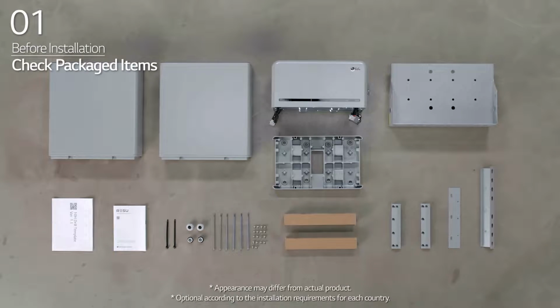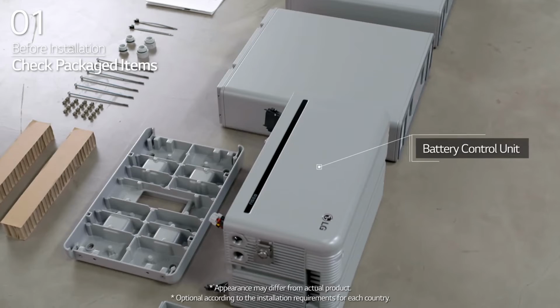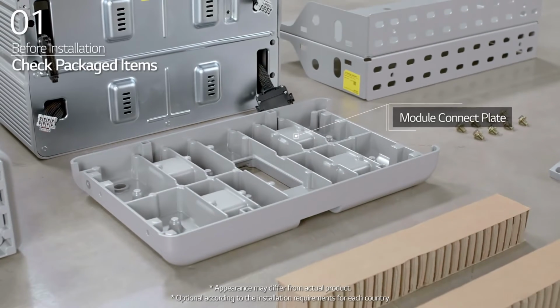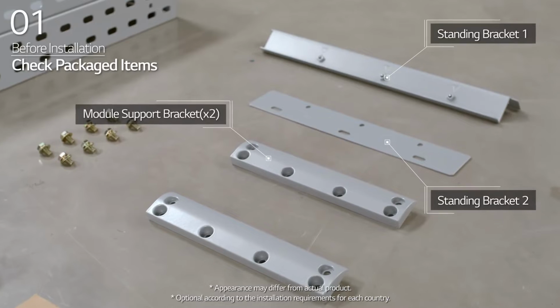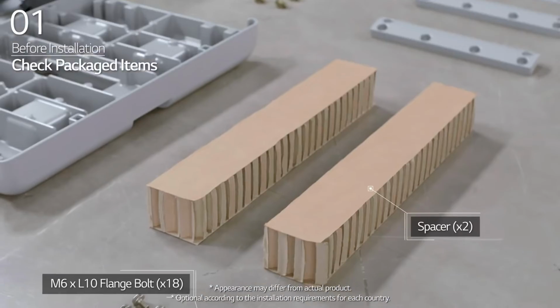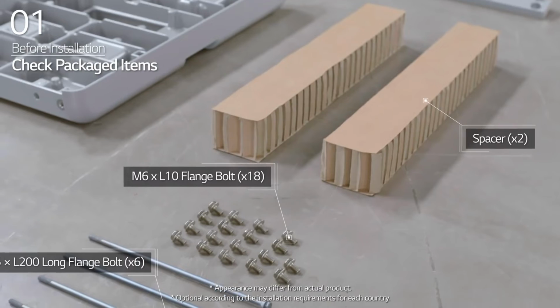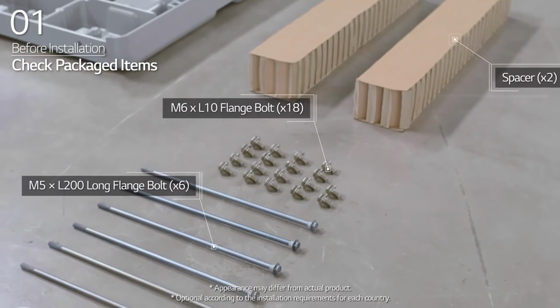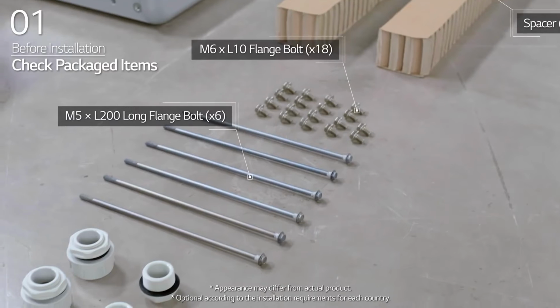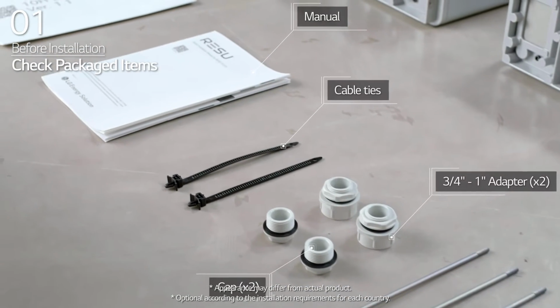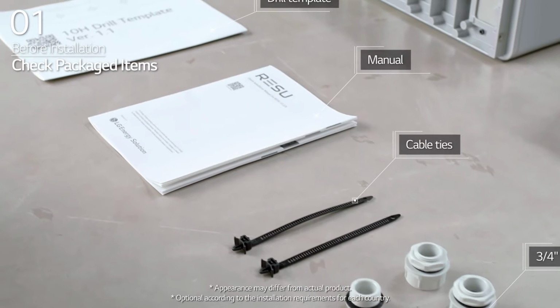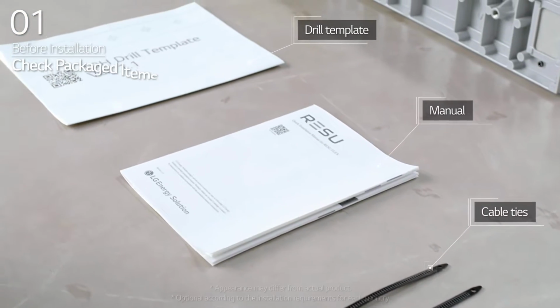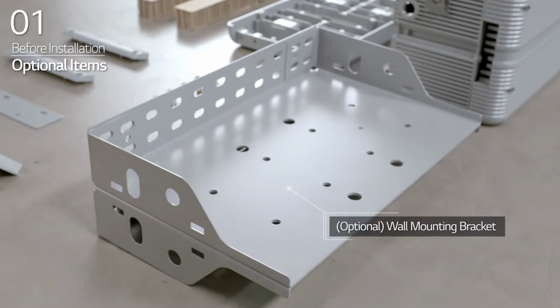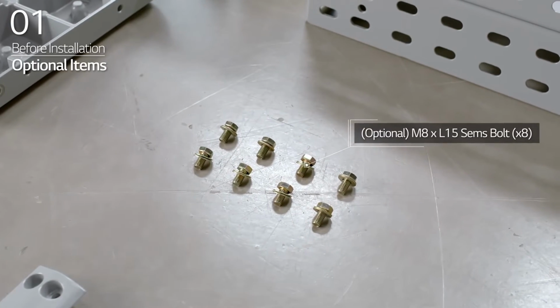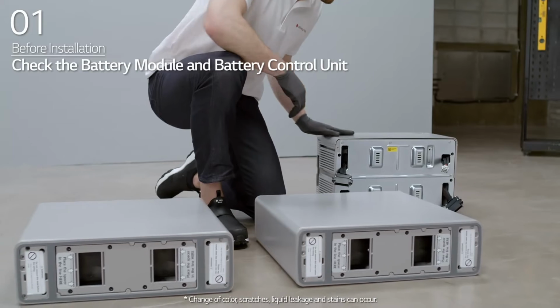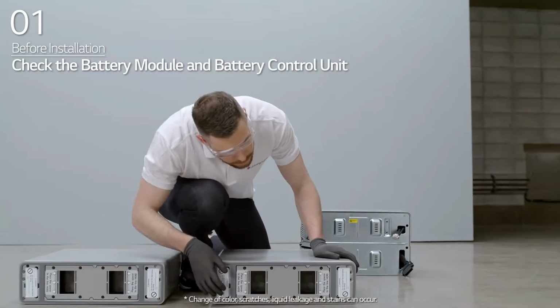In the box, you will find the battery modules, battery control unit, module connect plate, module support brackets, standing brackets, spacers, M6 by L10 flange bolts, M5 by L200 long flange bolts, 3/4 to 1 inch adapters, caps, cable ties, manual, drill template. For wall-mounted installation, you need to prepare the optional items. Before installation, check the battery modules and battery control unit to see whether they have any damage.